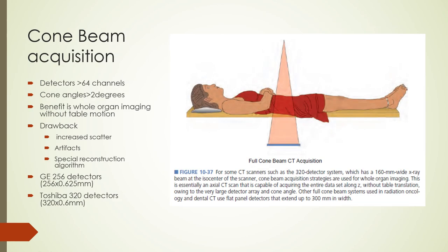Newer CT scanners often feature detectors with more than 64 channels. As more detector channels are added, the effect of the cone angle becomes significant, requiring specialized cone beam reconstruction algorithms — called cone beam CT. Cone beam acquisitions allow imaging of large moving structures like the heart with a single axial rotation, but drawbacks include increased scatter and the potential for cone beam-related artifacts.